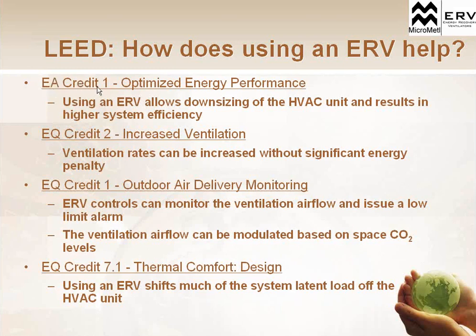If we break that down, under energy and atmosphere, you can get optimized energy performance on your system, because we mentioned using an ERV actually reduces the size of your HVAC system, like your rooftop unit. Instead of maybe previously having to have a 6-ton unit to take care of that summer and winter load, maybe we can now replace that unit with a 5-ton unit. So we've reduced the size of our HVAC system, and reduced the amount of compression or heating required using the energy recovery unit. Increased ventilation: because we're able to bring in more outside air since we're pre-treating it, preheating or pre-cooling it, we can actually increase those ventilation rates without taking a hit on efficiency. So we're increasing ventilation, which increases indoor air quality, which is obviously a great thing for a green design.